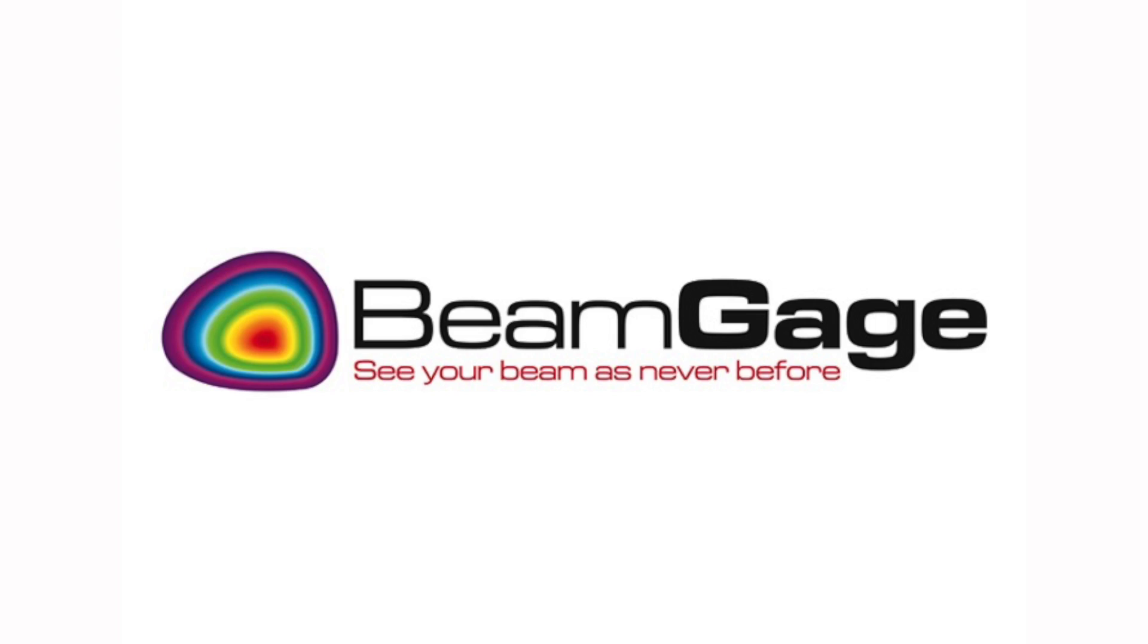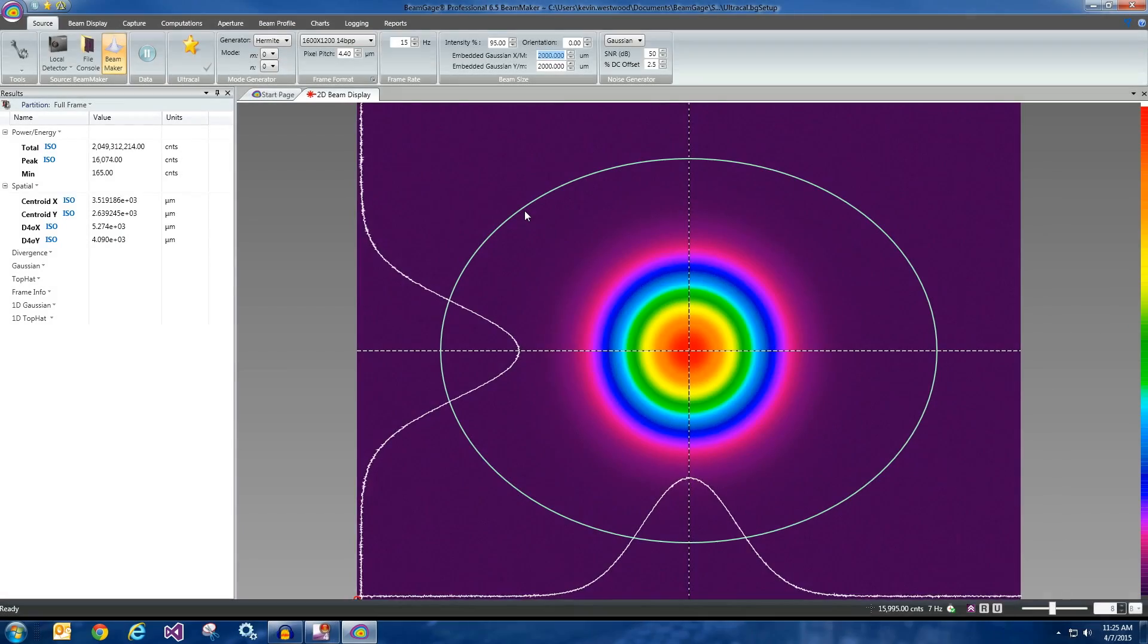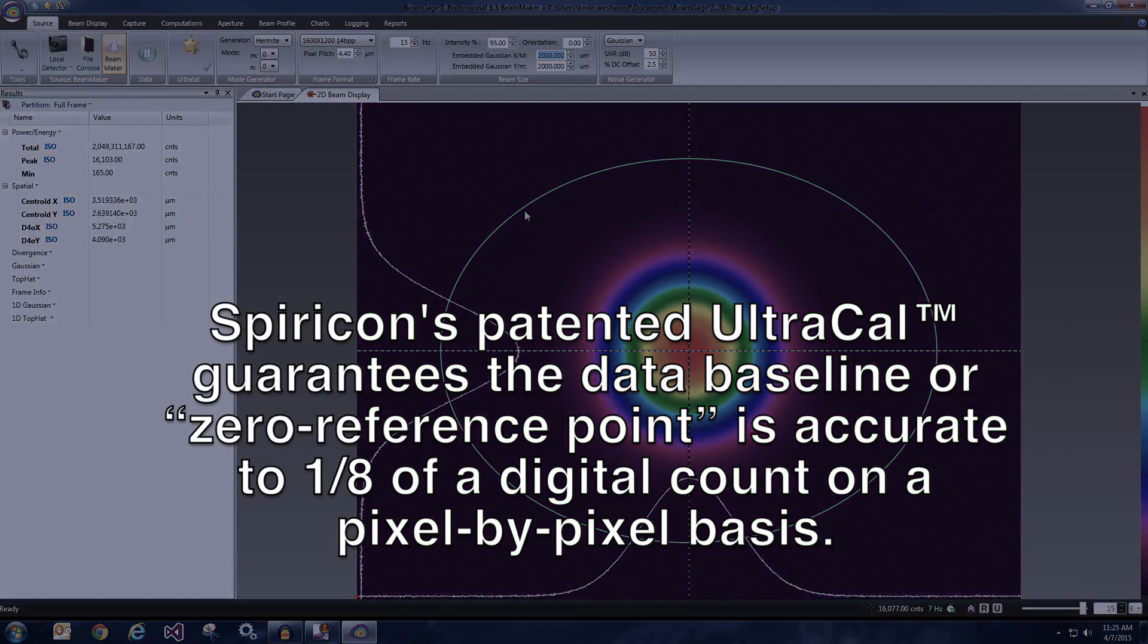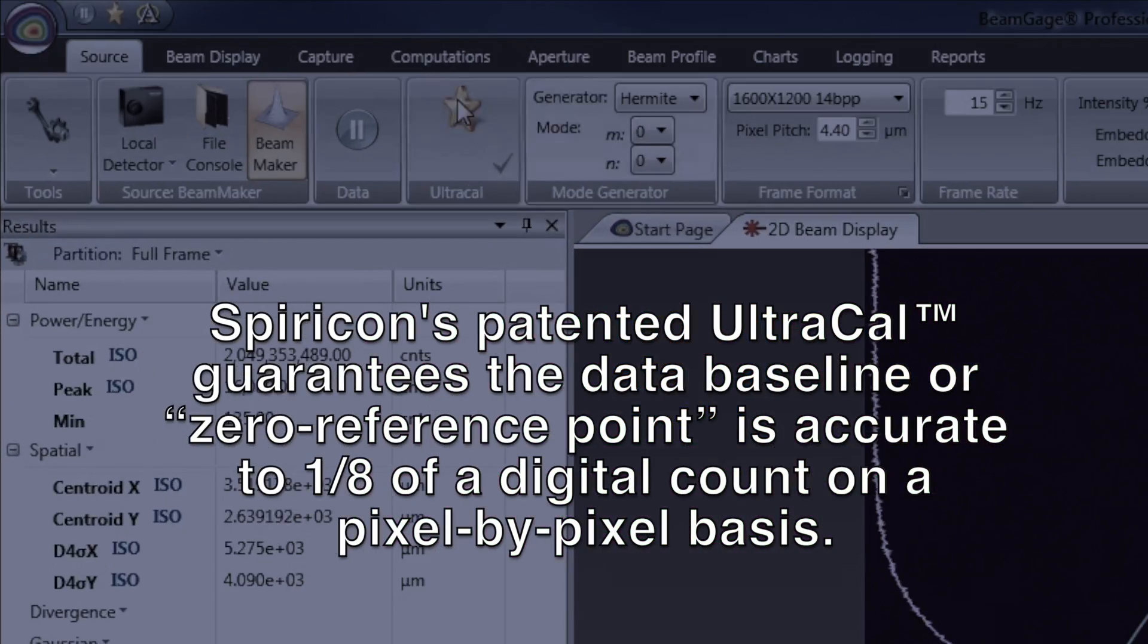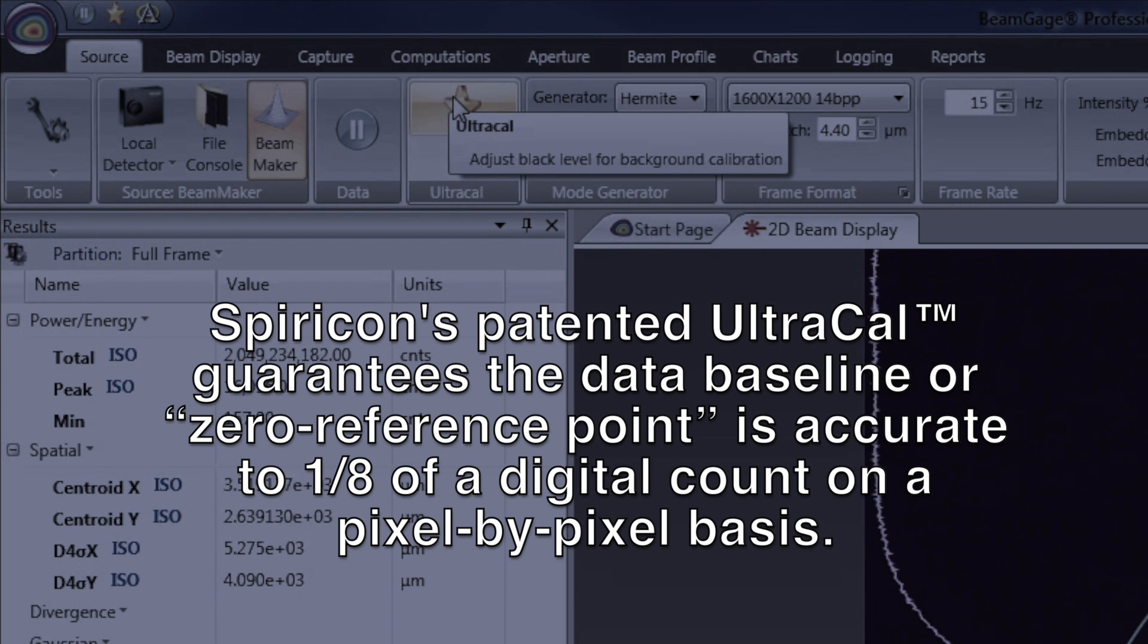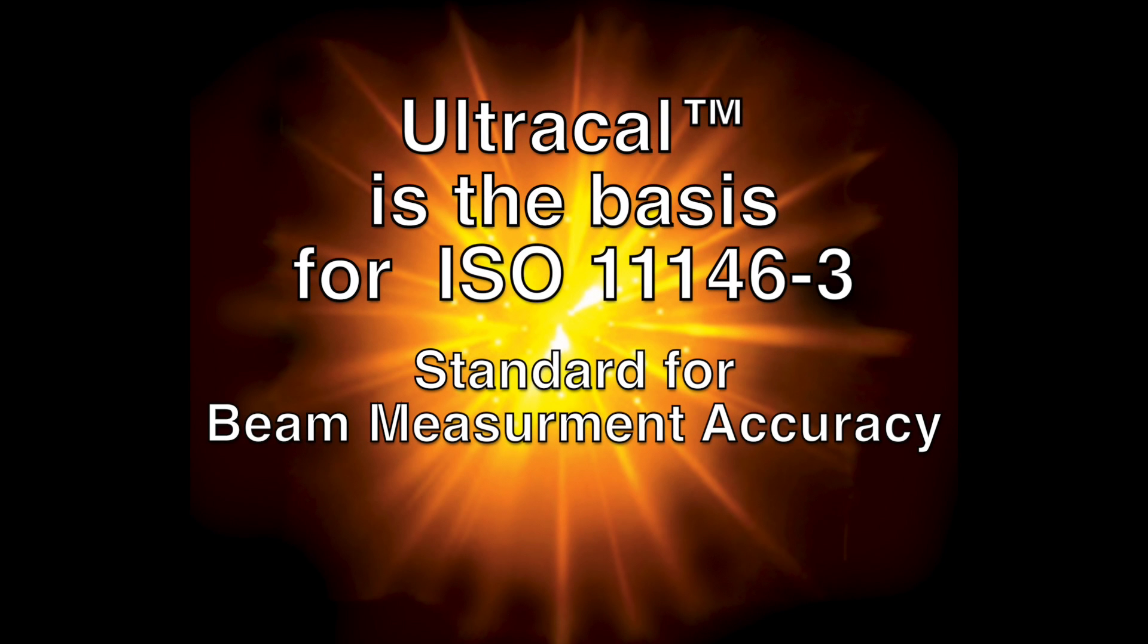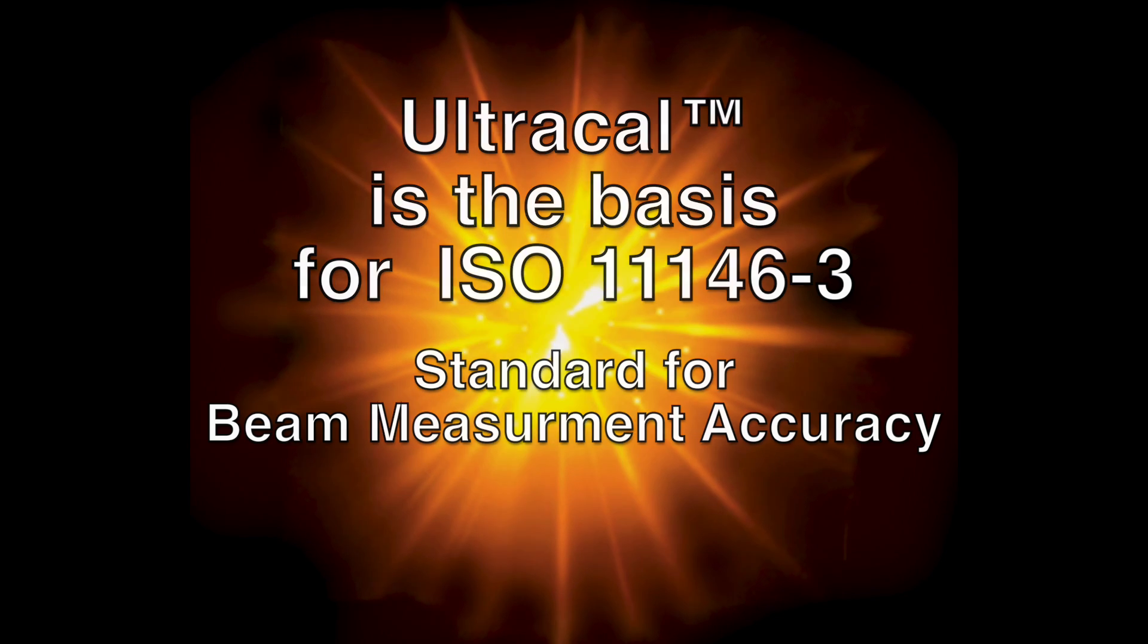BeamGage uses our patented UltraCal algorithm to properly set the data baseline or zero reference point to as accurate as one-eighth of a digital count on a pixel-by-pixel basis. UltraCal helped establish the ISO 11146-3 standard for beam measurement accuracy.